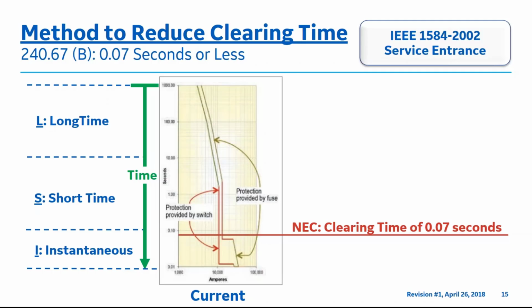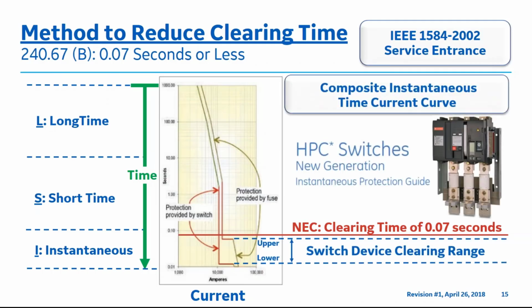A time current curve like the one shown here can be achieved through a composite time current curve clearing in the instantaneous region of the time current curve, which is demonstrated here for both arcing faults, protection provided by the switch, and bolted faults, protection provided by the fuse. In the lower band is a minimum switching device commit time that has begun to measure the arcing current fault event, also known as the initiation point. The upper band is the maximum clearing time, which clears the arcing current fault at 0.058 seconds. The orange arrow shown here demonstrates the 42,000 amp fault clearing at less than 0.07 seconds.